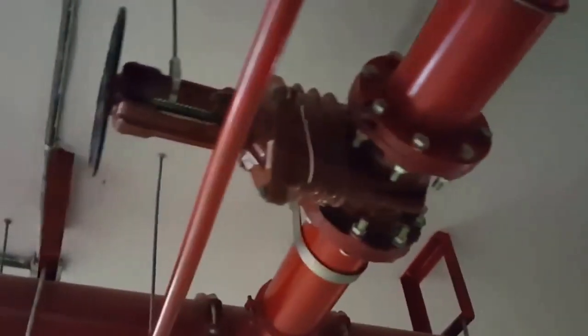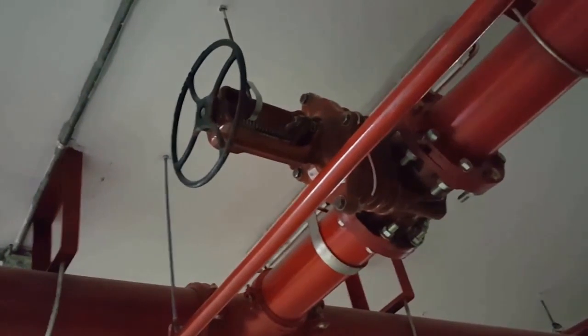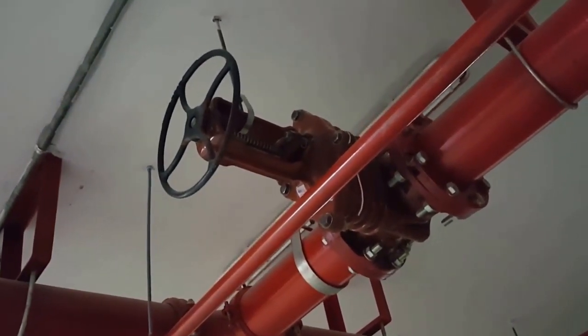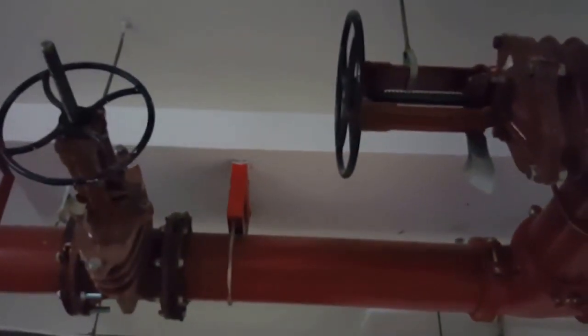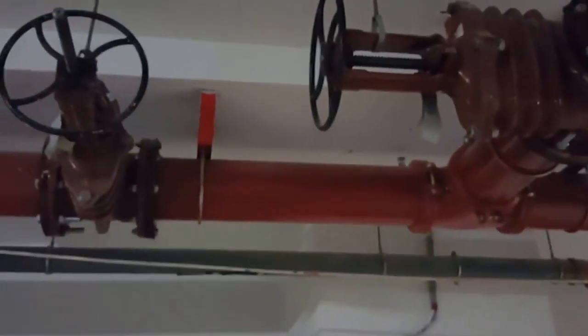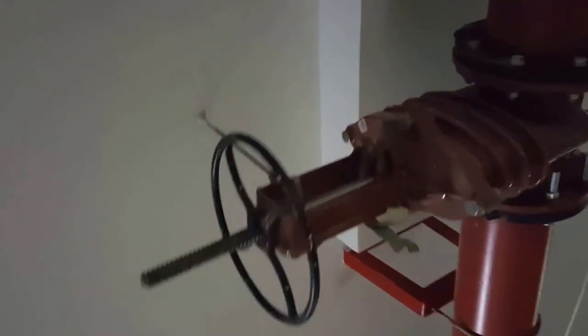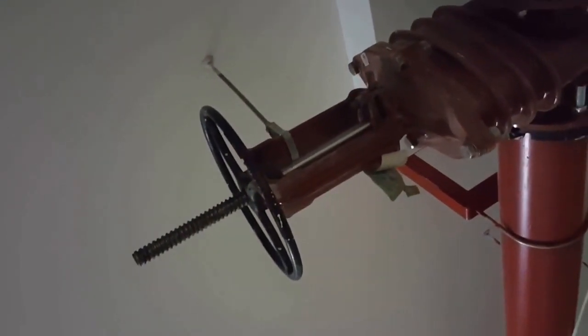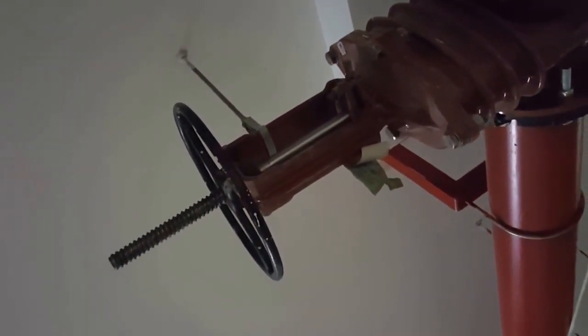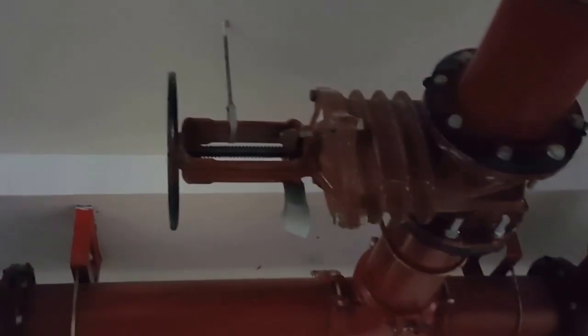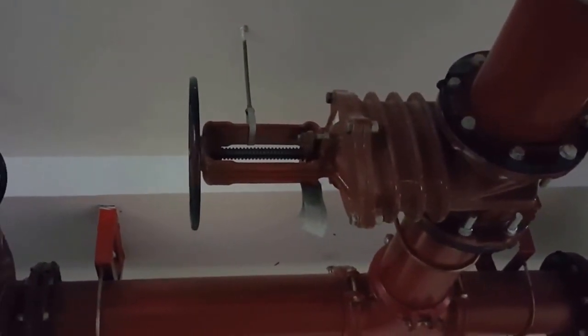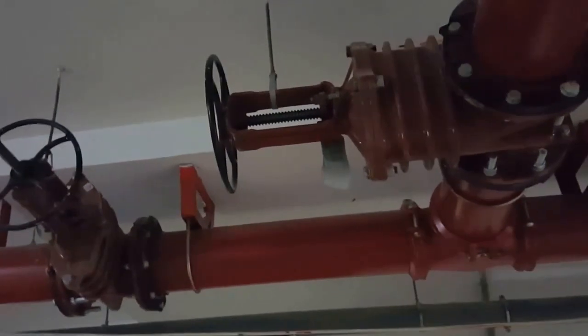This is an OS&Y valve that functions like a gate valve. See here, this valve rod is going up. When the rod is coming out from the lever it means this is open. When this rod is not coming from the lever, the pipe is closed, so the gate valve is closed.